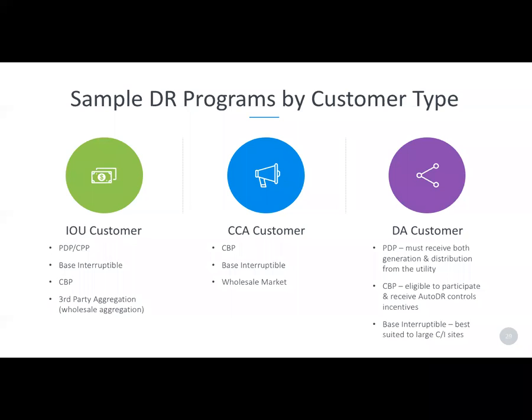by the utilities. And then lastly, and this ties into the project John was discussing earlier, that's wholesale market participation. Here, demand response providers are able to bid aggregated customer demand reductions into the wholesale market. So again, similar to capacity bidding, you would work with a third party, also called an aggregator, to implement this strategy. Again, some of the benefits of this is it's more akin to continuous DR. There's a lot more flexibility in how you participate. You can participate year-round instead of just during the summer season. And so this would enable participation in the spring, winter, and fall months instead of just the summer months.